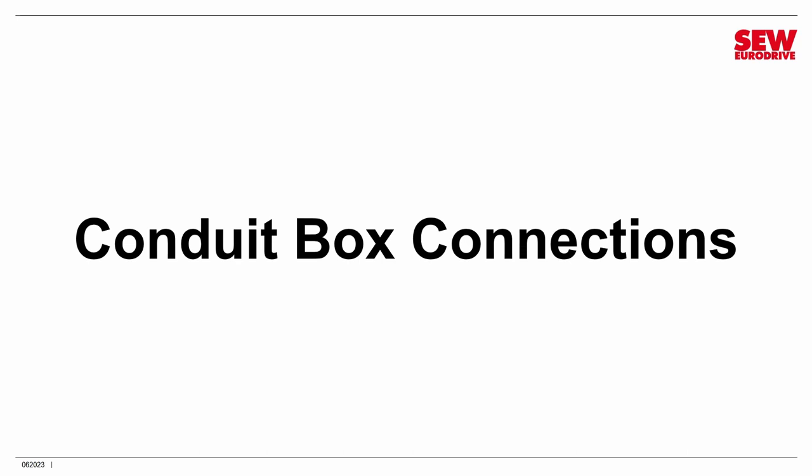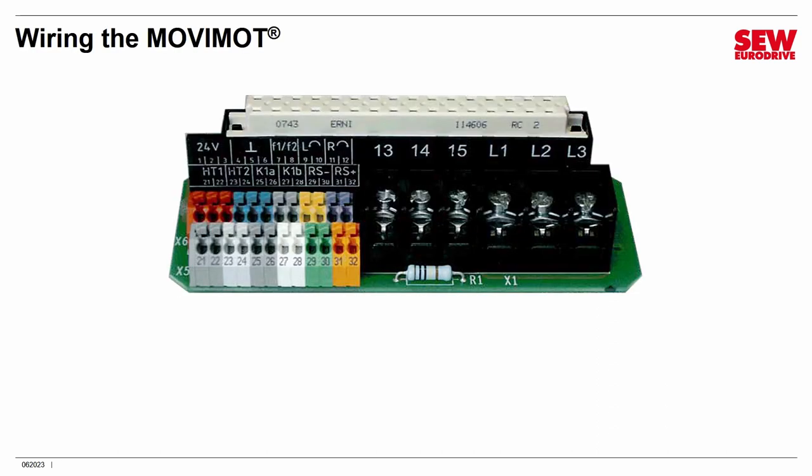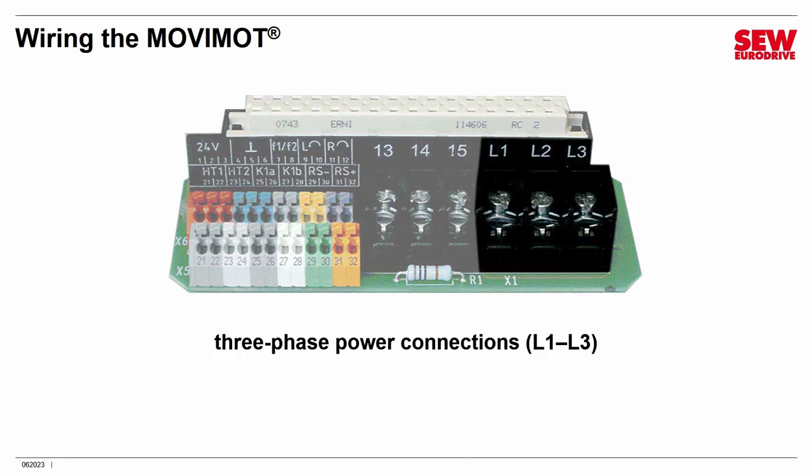Let's talk about the different electrical connections you make inside the conduit box part of the MOVIMOT. You will see these when you remove the control head — it's a circuit board with a number of terminal connections on it, and there's also a connector at the very top that mates with the control head. The big connectors marked L1, L2, and L3 are the connections for three-phase power, so this is where you connect your line power. There isn't a protective earth connection here — it's in another location.